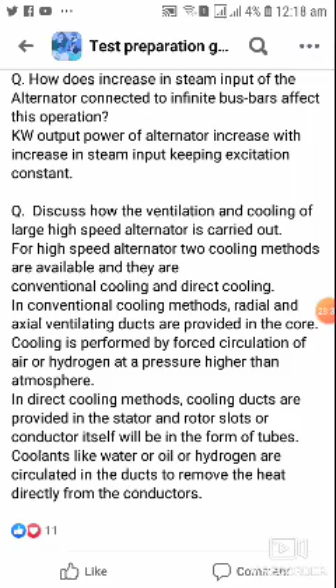Question number 52. Discuss how the ventilation and cooling of large high speed alternator is carried out. For high speed alternators, two cooling methods are available and they are conventional cooling and direct cooling. In conventional cooling methods, radial and axial ventilating ducts are provided in the core. Cooling is performed by the forced circulation of air or hydrogen at a pressure higher than the atmosphere. In direct cooling methods, cooling ducts are provided in the stator and rotor slots or the conductor itself will be in the form of tubes. Coolants like water or oil or hydrogen are circulated in the ducts to remove the heat directly from the conductors. It is all about this video.